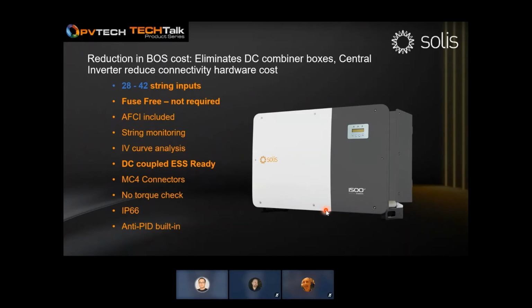Now, once we replace it with the Solis 255 kilowatt, what you get is a 28 to 42 string input device with fuse free. What that means is, when you install this, you do not need DC fuses. It's no longer required. AFCI is built in, as well as string monitoring. And from the string monitoring, you will get IV curve analysis, a remote IV curve analysis. This unit is DC coupled storage ready with built-in MC4 connectors, which are pre-terminated, easy to replace, and require no torque check. The whole unit is IP66 rated with anti-PID built in.